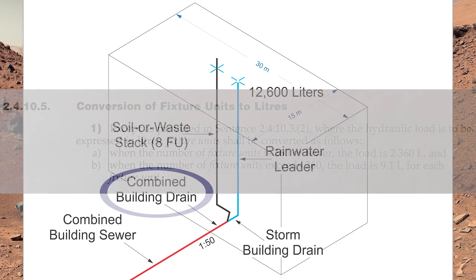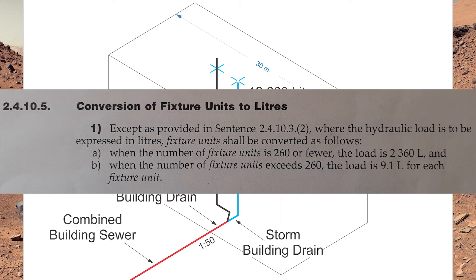We need to look into the code at clause 2410.5: conversion of fixture units into liters. Except as provided in sentence 2410.3(2), where the hydraulic load is to be expressed in liters, fixture units shall be converted as follows: (a) when the number of fixture units is 260 or fewer, the load is 2,360 liters; and (b) when the number of fixture units exceeds 260, the load is 9.1 liters for each fixture unit.